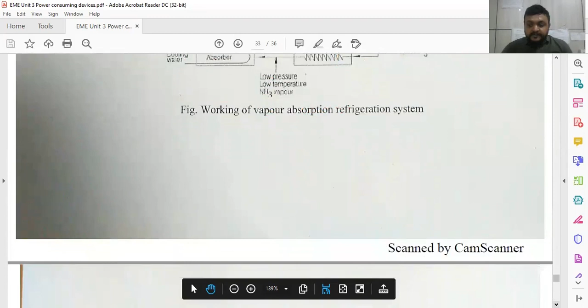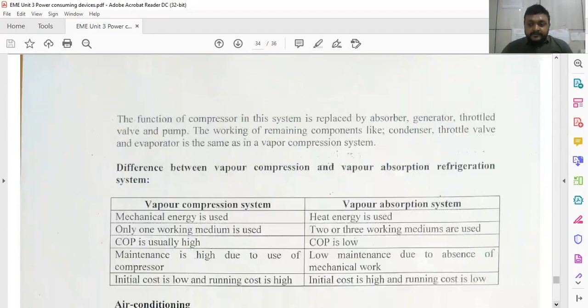Now here you have to see the fundamental differences between these two systems, the vapor compression system and the vapor absorption system, on the left and right hand side. Here mechanical energy is used, here heat energy is used. And we are isolating the mechanical energy, so there is less maintenance. Maintenance is very high due to use of the compressor, but our main objective is to reduce the maintenance. So maintenance is almost nil due to the absence of mechanical work. COP is usually high in compression, and low in absorption. However, we are not achieving as much COP in the vapor absorption system, but for specific media and specific applications, we can go for that.